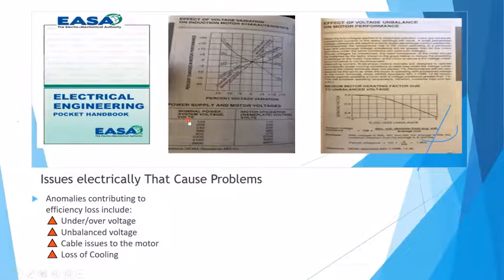I just highly recommend looking at it, because the factor that people lose track of is when the voltage changes. Again, say what the generator is really designed for is 480 volts, and the motor was designed for 480 volts. If the power getting to the motor isn't 480 volts, the motor, for what it's designed, feels starved. As soon as the voltage drops, you still have the torque going out the shaft, so what happens is the current rises. The motor winding has a certain resistance, and that's where the heat comes from. So you have to be really careful of under voltage and over voltage.